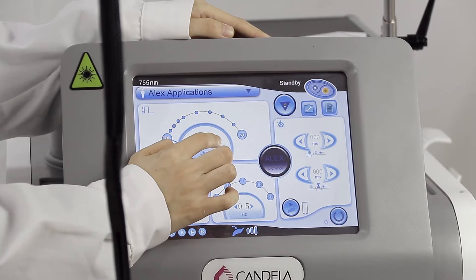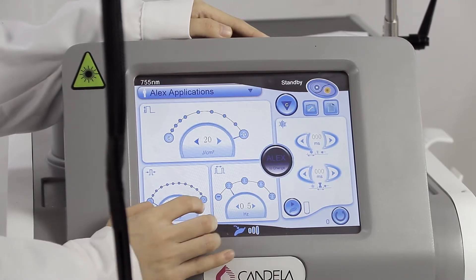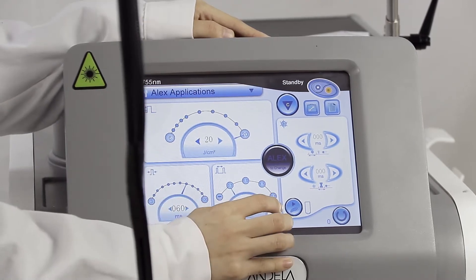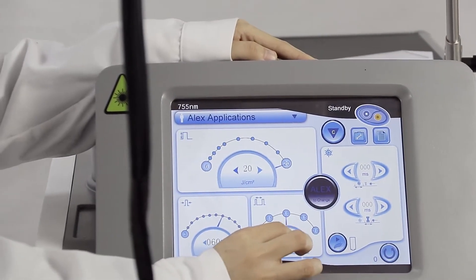We can adjust the energy from 6 to 20. We can adjust the pulse width from 3 to 100. And the frequency can be turned from 1.5 hertz to 2 hertz.